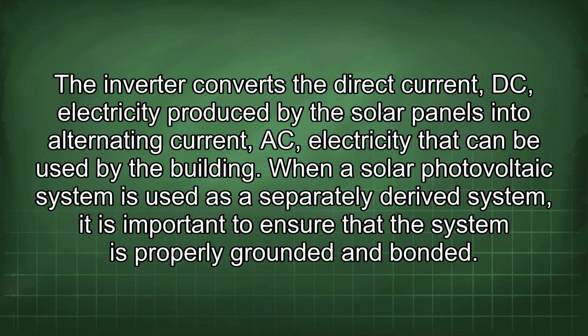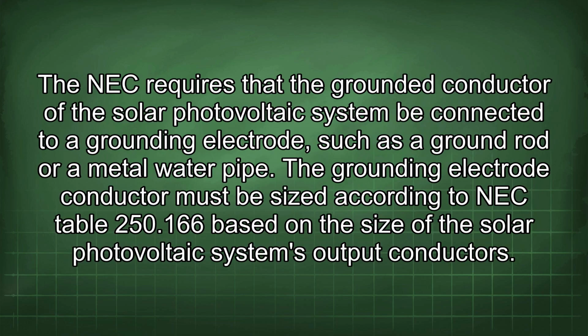When a solar photovoltaic system is used as a separately derived system, it is important to ensure that the system is properly grounded and bonded. The NEC requires that the grounded conductor of the solar photovoltaic system be connected to a grounding electrode, such as a ground rod or a metal water pipe.